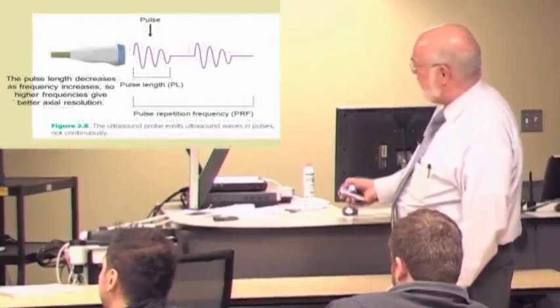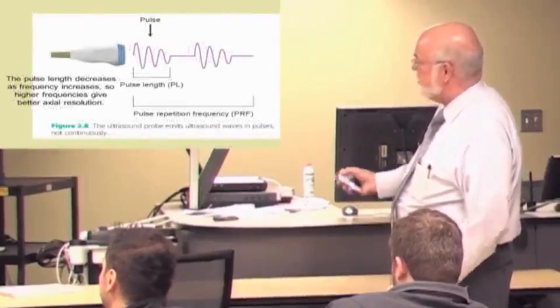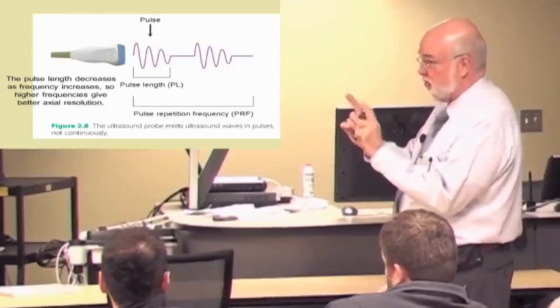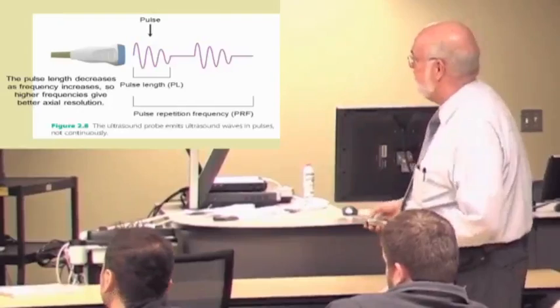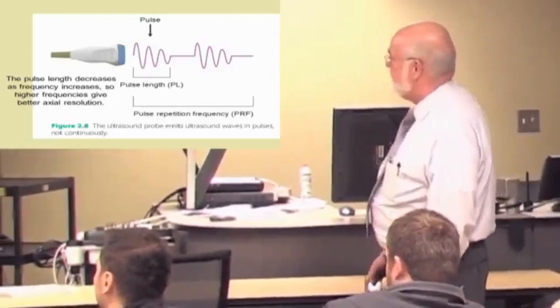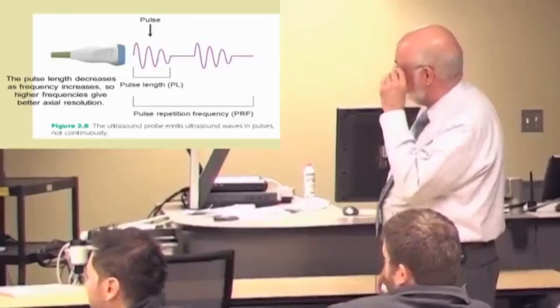Now, if you think about it, if the frequency is higher, those are going to be scrunched together, so it's going to be a shorter pulse length and better resolution, so that's a useful thing to keep in mind. So higher frequencies do give us better axial resolution.